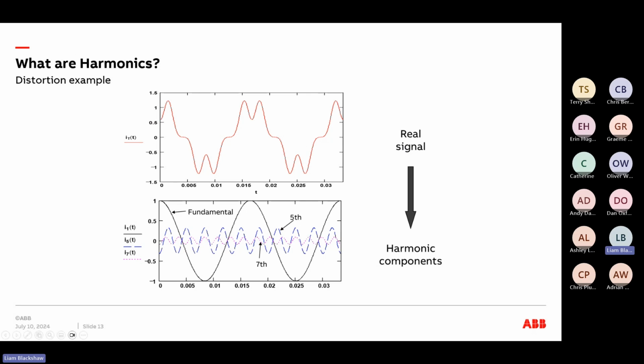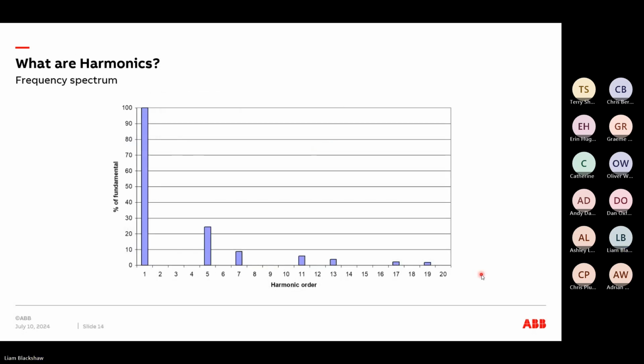So you can see here, I'm just going to get my pointer now, for example. If we took it here, we're looking at the peak value of our fundamental plus our minus, and our minus here. When we put that in line, we get that slight little dip there. So we're summating those signals at a given point, or all given points. As I said before, when we look at harmonics, we never really look at waveforms. Maybe if we're doing a more detailed analysis to understand a particular issue. But when we want to do a report, for example, we always look at what we call the frequency spectrum.